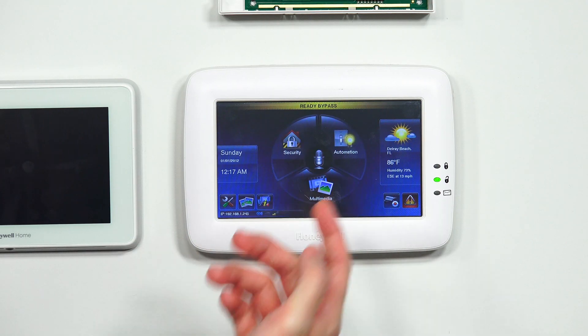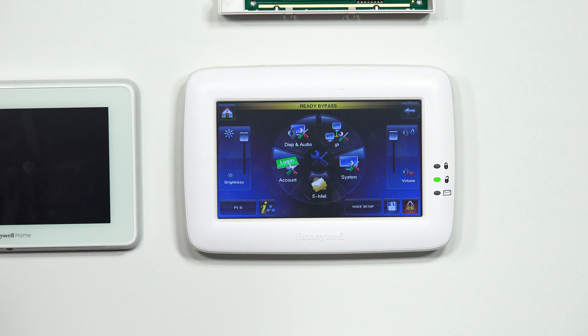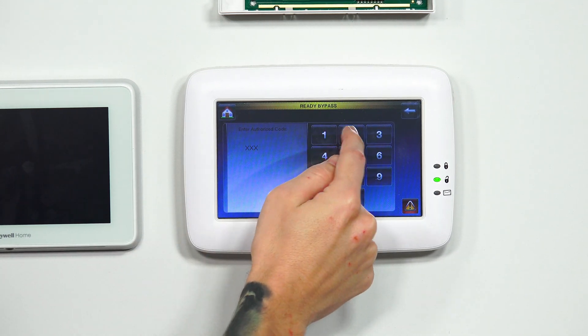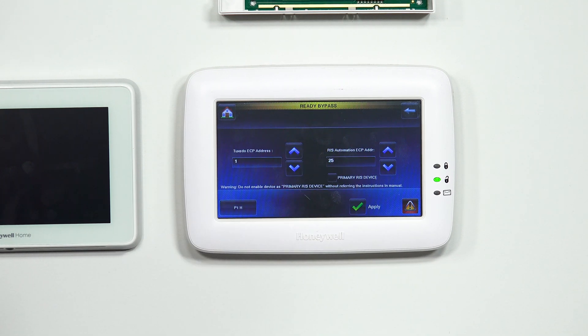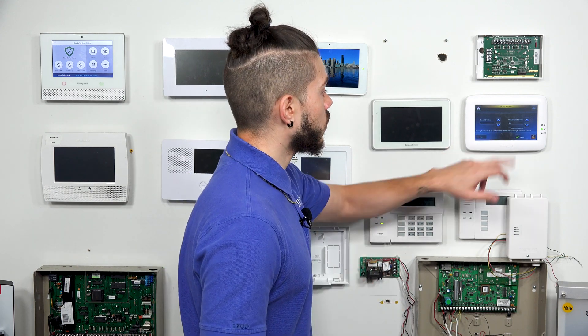You can change it using the down arrow keys. Just be aware that if you wait too long, it'll back out. So again, just to recap: wrench icon in the bottom left corner, go to System, CS Setup, enter 4112 — super easy to get to. Go to ECP address and there you can see all your information. Make sure you have this noted down. It's very important that you do not have two Tuxedos on the same ECP address, or you will get ECP conflicts. That's not the only thing that may cause an ECP conflict — you might also have a wiring issue. Always make sure you're troubleshooting with technicians so you can actually diagnose what's going on.